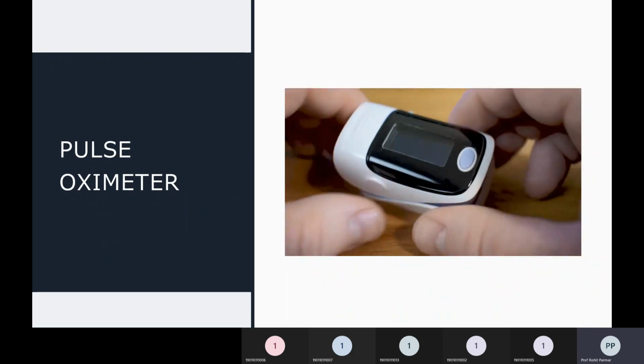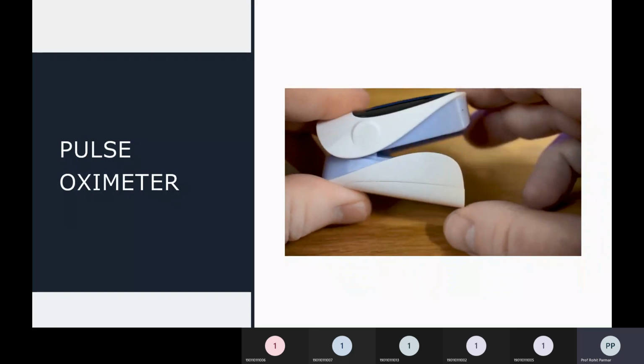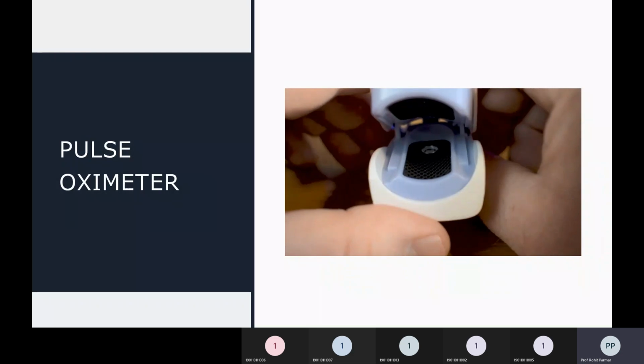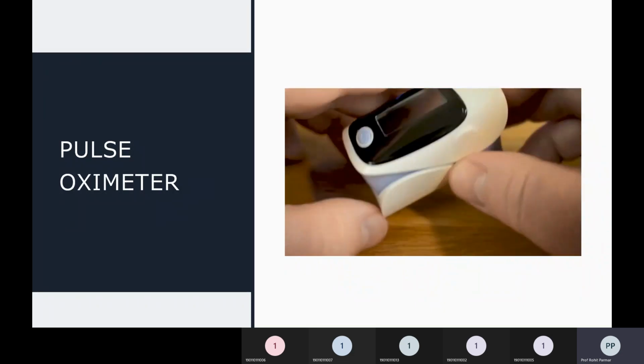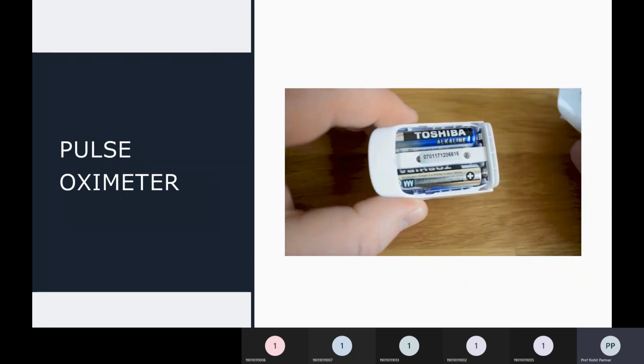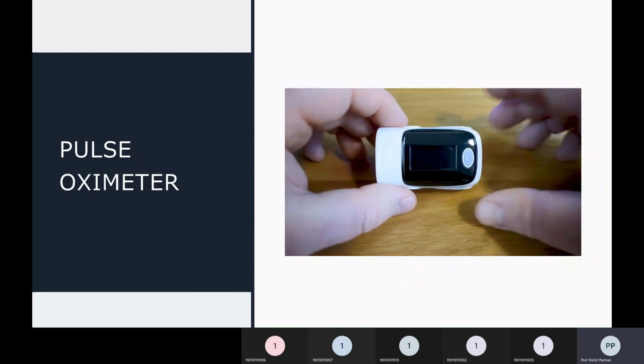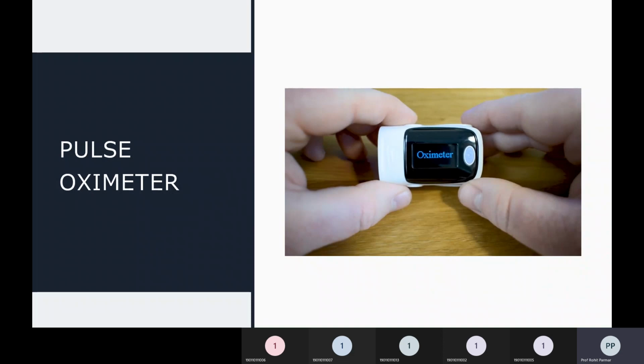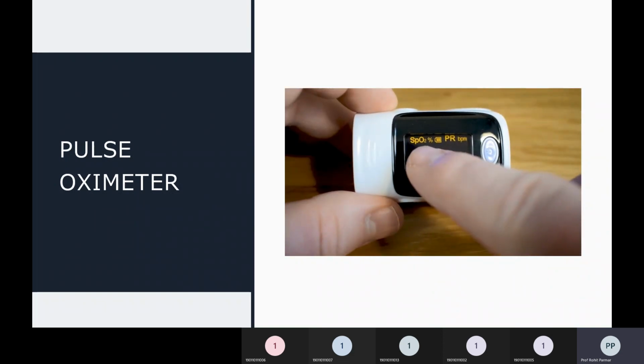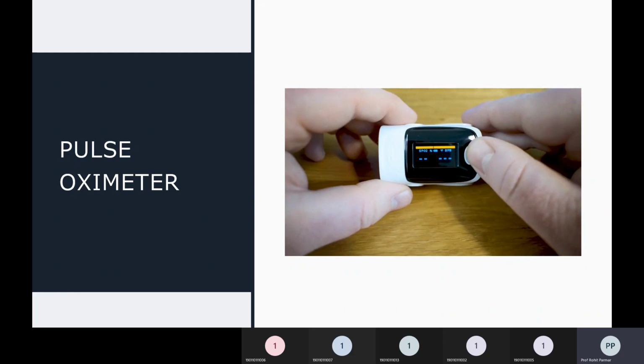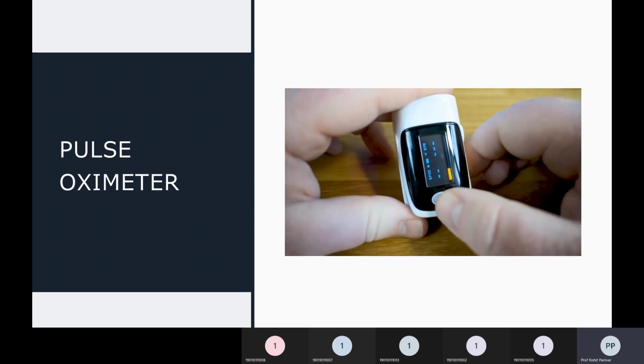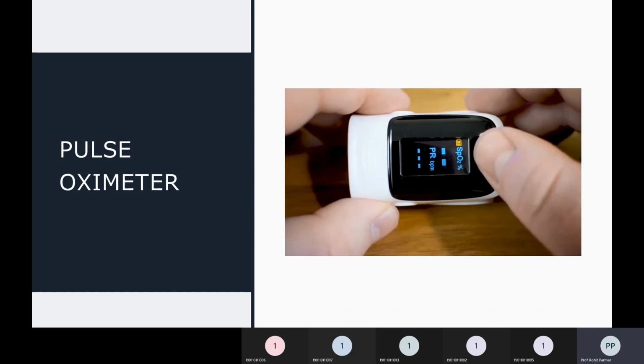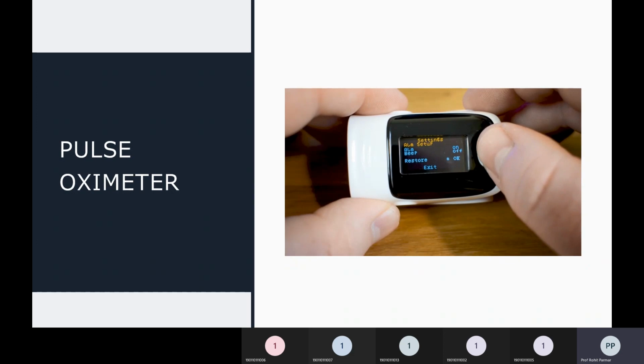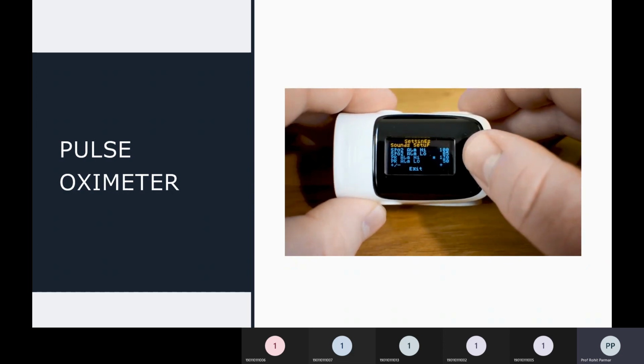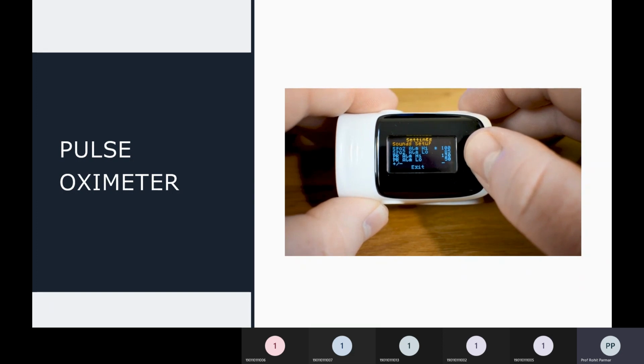one. This particular oximeter is made out of 2 plastic parts that are connected with a hinge. It has a single button for all its functions and one colored LCD display. By pressing and holding the hinged part, the infrared sensor is visible. Everything is powered by 2 AAA batteries. Now let's take a look at how it works. By pressing the button once, the unit turns on and information appears on the screen. In this case, besides the oxygen amount, we also have a pulse meter function. By pressing the button again, you scroll through the different screen orientations available to find the one that suits you the most. The unit will turn off by itself when not in use. In order to enter the menu, you press and hold the button for 3 seconds. Here you can set the maximum and minimum accepted values for both the oxygen amount and the heart pulse. You can also customize the alarm effects of the unit.